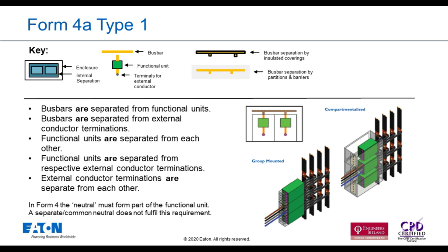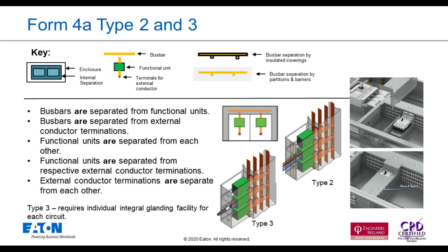In a compartmentalized solution, you can see that the functional unit is separated from the main bus bar in an enclosure. Each functional unit is separated from one another by the enclosure. The main bus bar is separated from the external terminals because it's got its insulating material, and each of the cable connections again go into the compartment. So on Type 2 and 3, with Type 2, we're just moving away from insulating the bus bar to covering the bus bar with a barrier or a partition. And Type 3, the only difference here is that each functional unit must have its own gland plate. So we can't use a common gland plate to comply with Type 3.